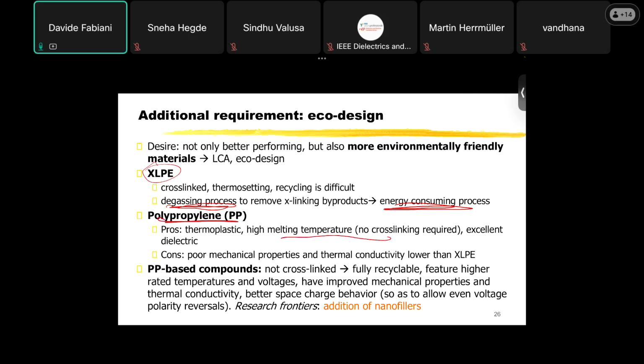The only problem is that the mechanical properties are quite poor, it's a very rigid material, and also the thermal conductivity is much lower than XLPE. But now there are polypropylene compounds using elastomeric or other non-cross-linked material that are fully recyclable. They have a higher rating temperature, can be used at higher voltages, and can have good mechanical properties and thermal conductivity. The research frontier for this kind of material is also the addition of nanofillers to further improve the properties of these polypropylene-based compounds.